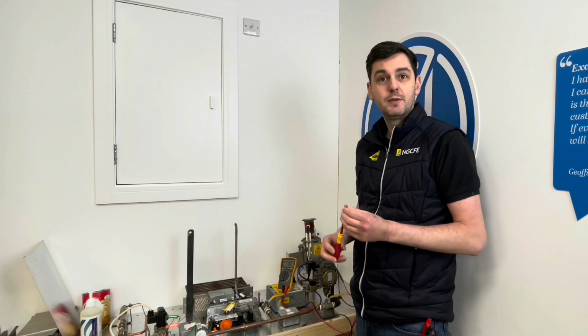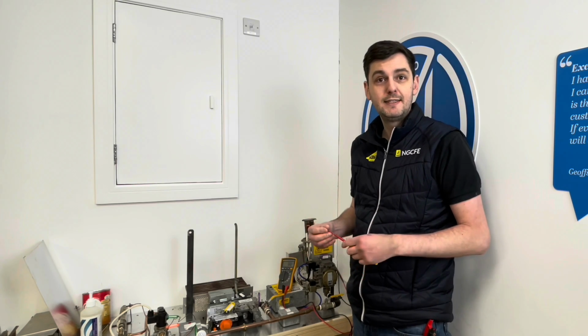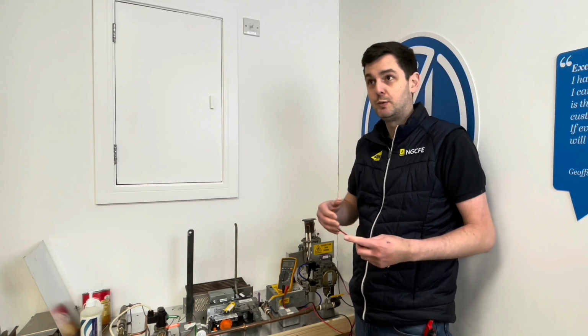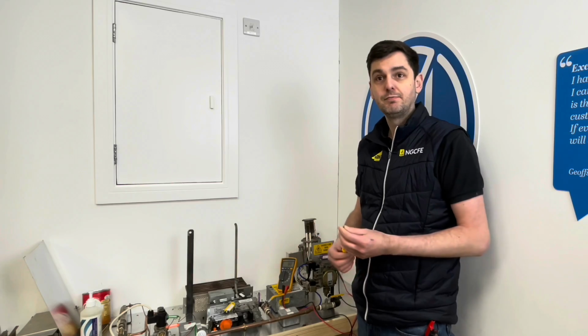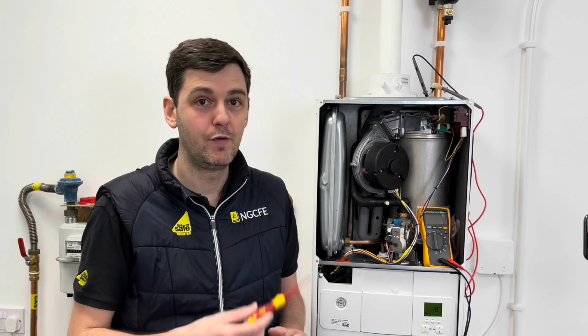Now we've done that, let's go and have a look at a Worcester 30i, and we'll see how we can use this test in a real world situation, in a real test. So we've arrived at Mrs. Smith's house. She's got a Worcester 30i ERP. Over the last 10 years, there's been more of this boiler installed than any other boiler. So the chances are you are likely to come across this fault on this boiler at some point. It's presenting us with an EA fault or an FA fault.